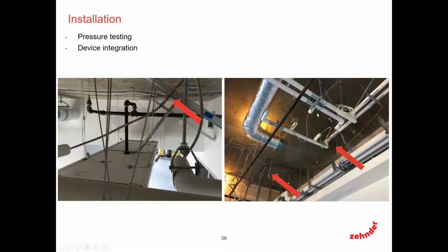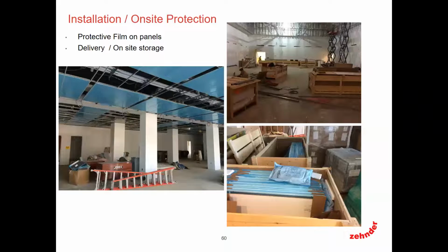The other thing I want to point out real quick is the other option when you run your supply and returns. The mechanical contractor runs the supply and return, and you can connect the supply and returns with flexible hoses. So here's your supply. The hose is connected with a 12-inch, half-inch piece of copper, push-to-connect fitting. Close it, pressure test the loop, and then move on. Once the active panels are installed, they can go back, take those hoses off, and then hook them up to the actual circuits themselves. So there's some flexibility there with the install too, depending on how the trays are going through.